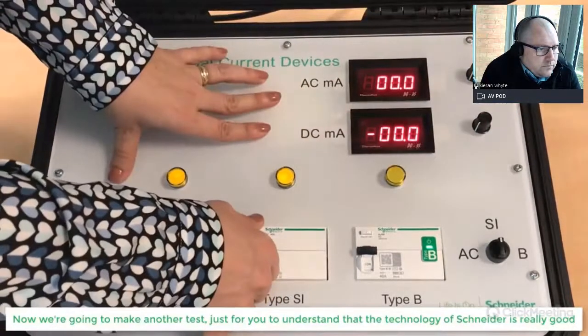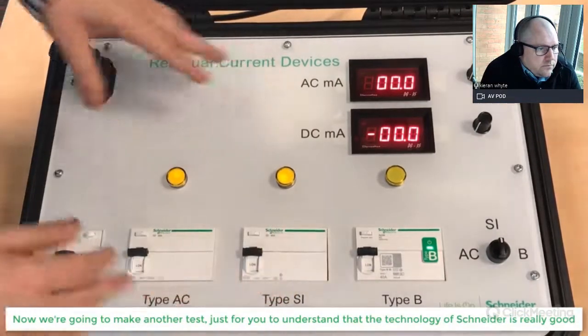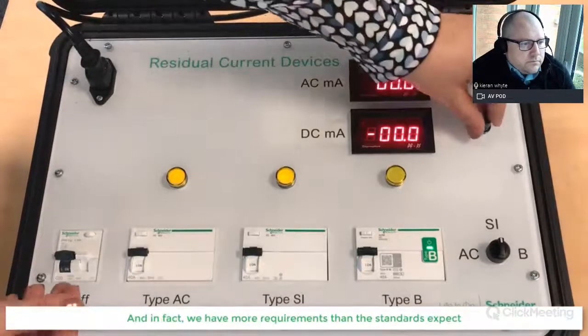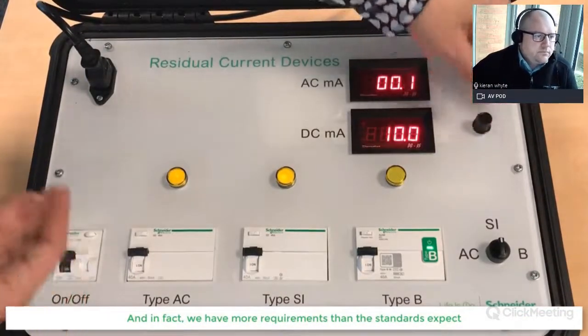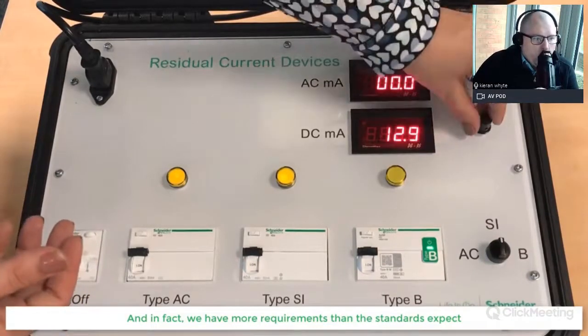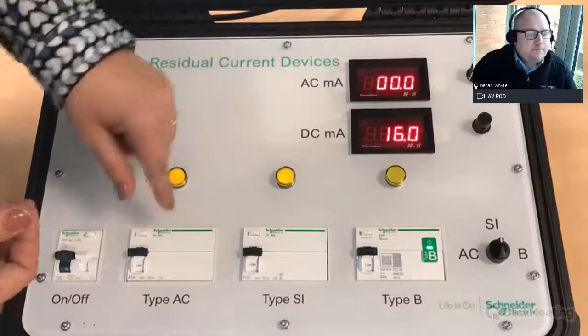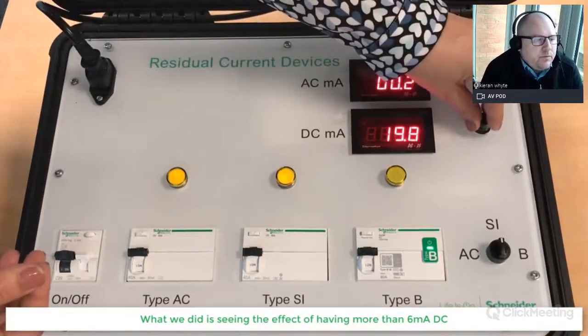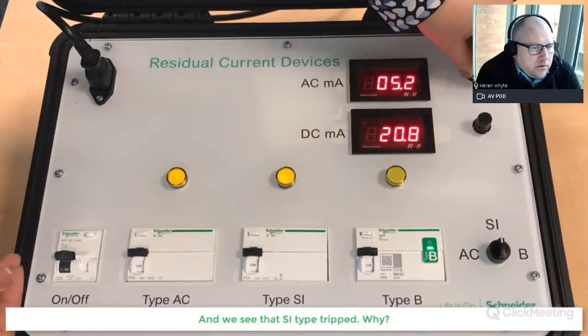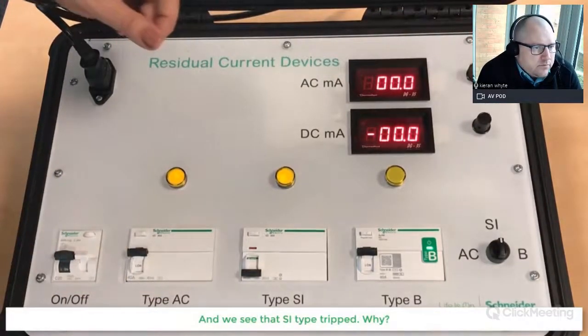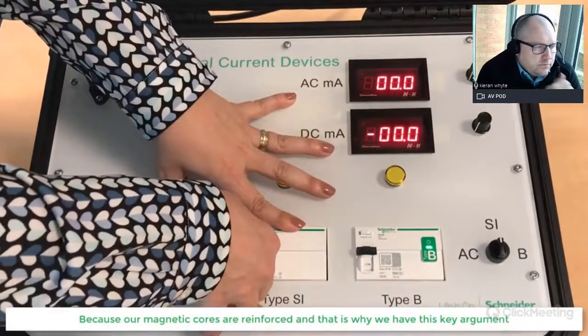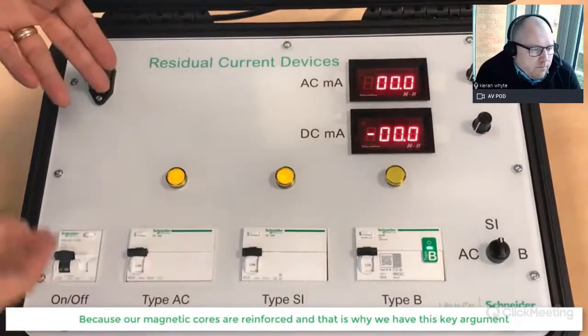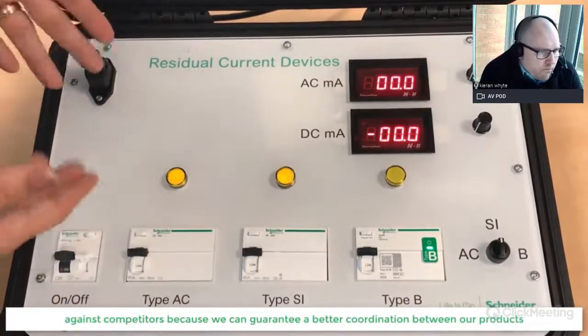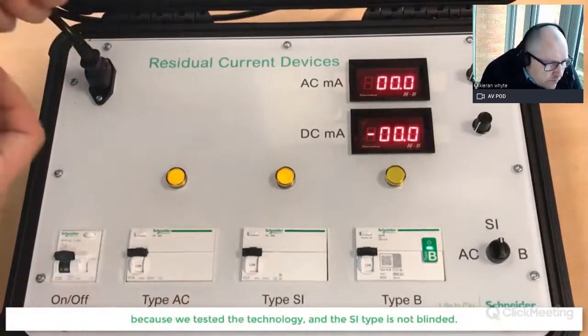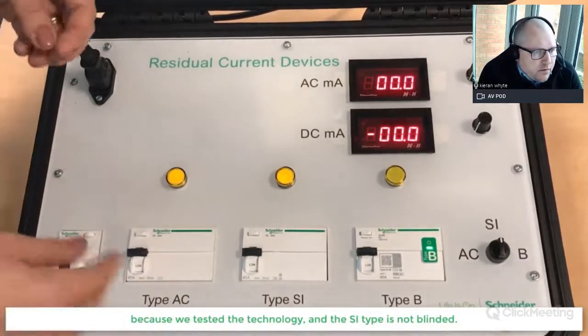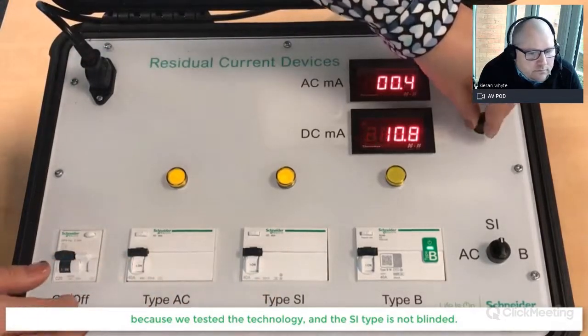Now we're going to make another test, just for you to understand that technology from Schneider Electric is really, really good. In fact, we have better and more requirements than the standards regarding our products. So what we did is to see the effect of having more than 6 milliamp DC. And what we will see is that the SI type trips. Why? Because our cards are reinforced, and that's why this is a key argument against competitors, because we can guarantee a better coordination between our products. We have tested and we know the technology, and we know that the SI type is not blinded, not even when you have a lot.